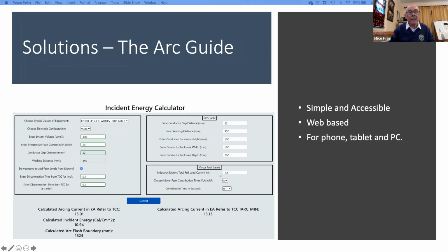But what we've also got on the right-hand side is a calculator to provide contribution from motor fault, which is quite important, particularly if all the equipment provided from that particular panel that we're looking to predict the incident energy level on is provided by motors, because there will be a significant motor contribution back into the arcing fault. So that takes care of it quite simply and quite nicely. And this other table, this is where you can enter all your own figures rather than a preset set of figures that you can just click on down here, like for low voltage switchgear or high voltage switchgear or wherever it might be.